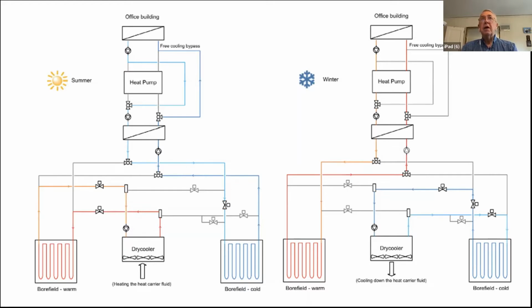So all of that is industry standard, and we're not showing anything different for that part of it. And likewise, the heat pump in all of these examples is a common mass-produced off-the-shelf water source heat pump. There are actually 3 names for that. Water source is one name, geothermal heat pump is another name, and ground source heat pump is a third name. They're all the same thing, except with slightly different temperature ranges, perhaps. All right, so we have examples now from Spain, from Italy, and from Belgium.